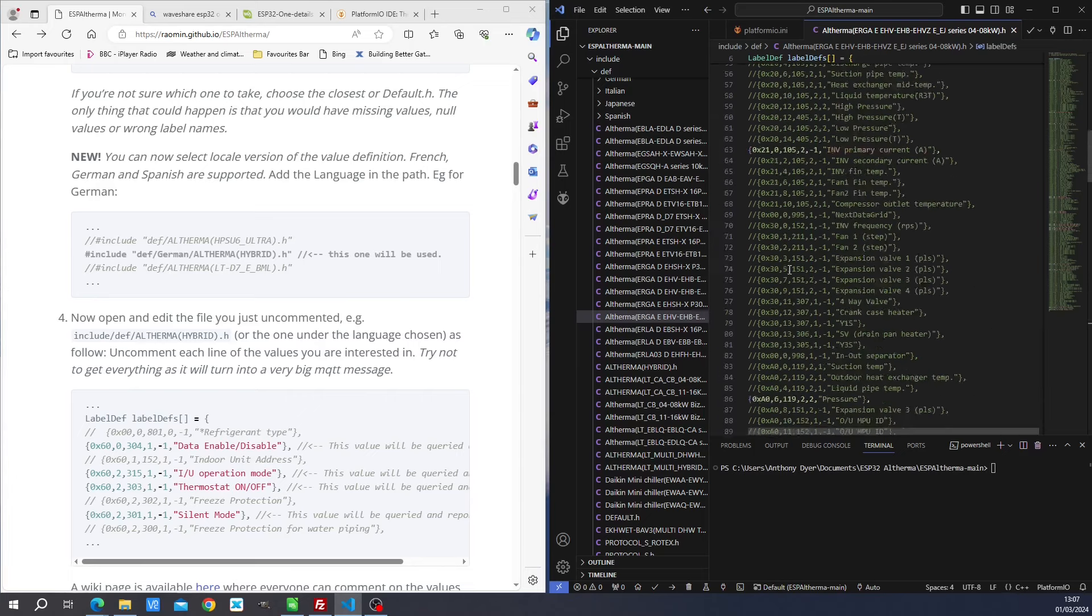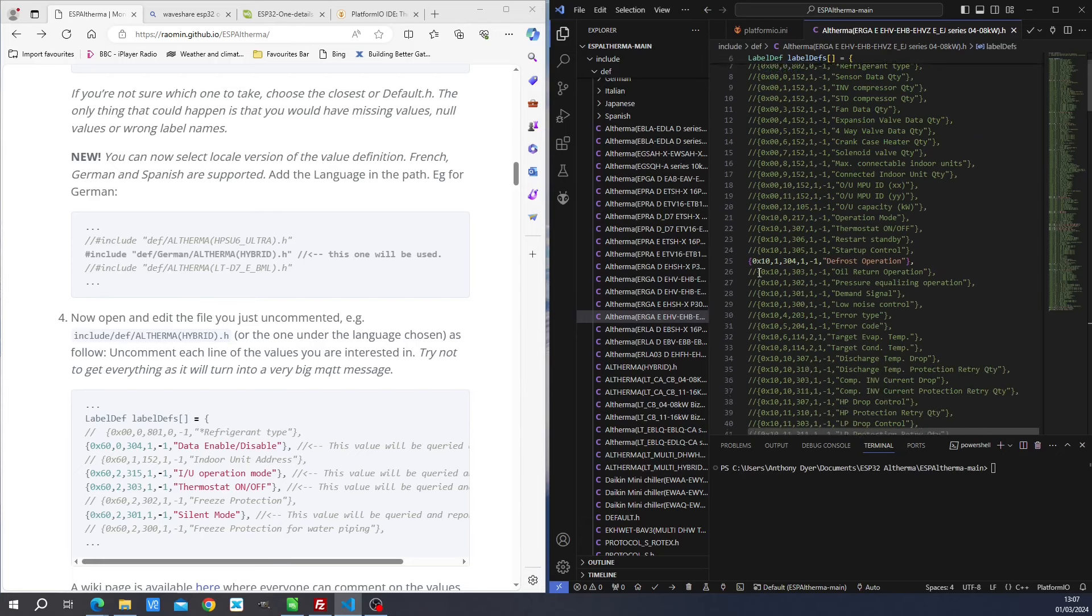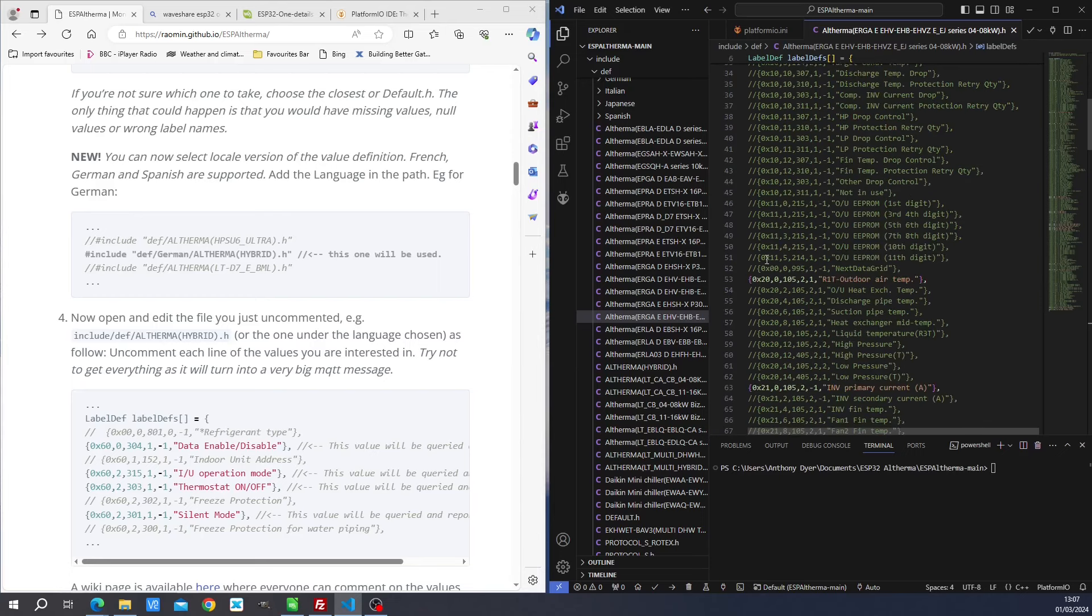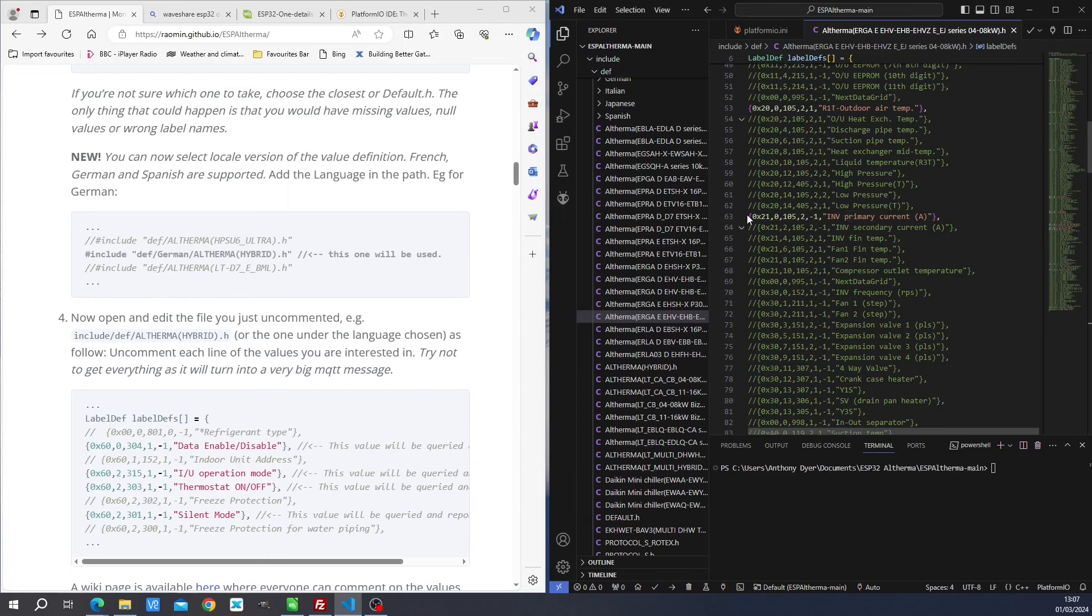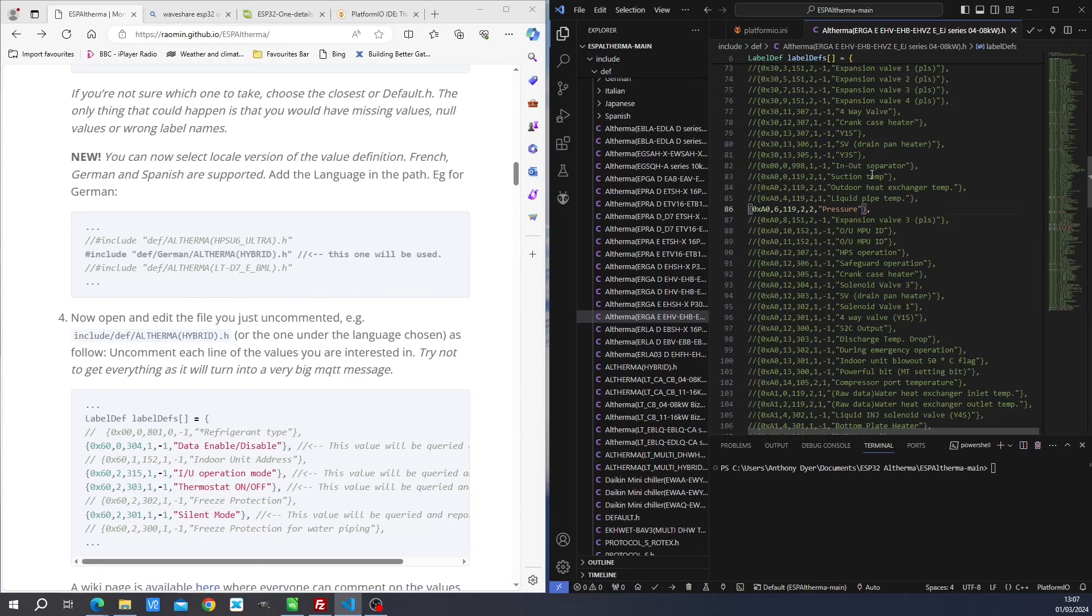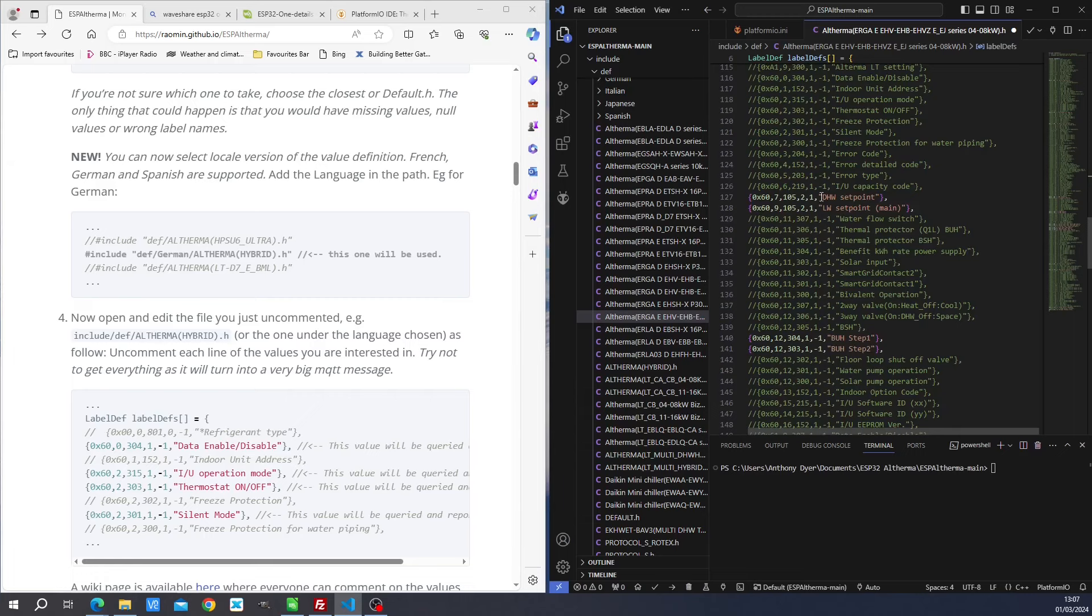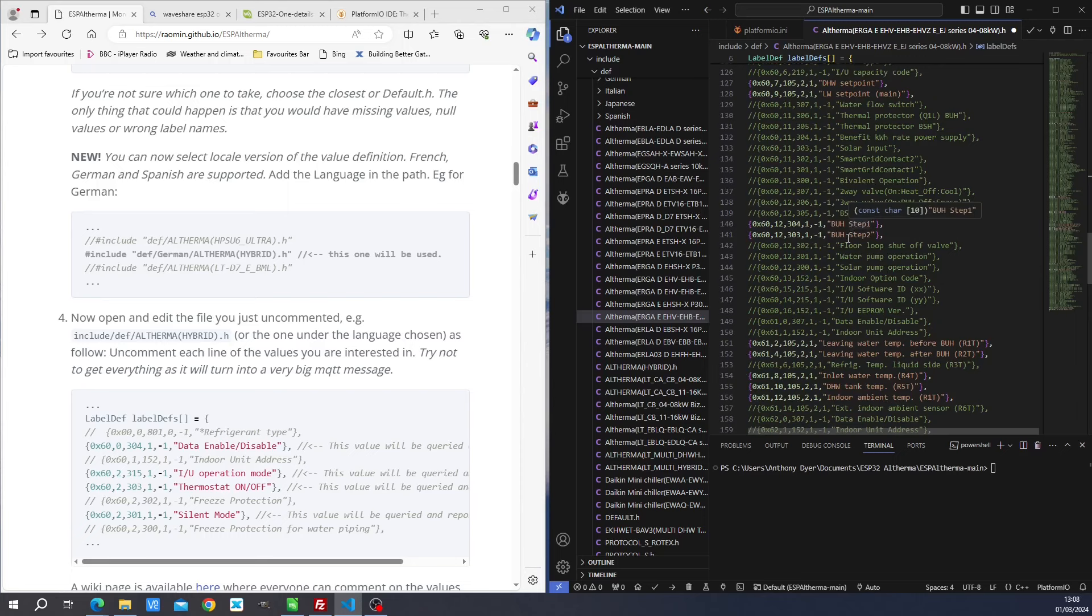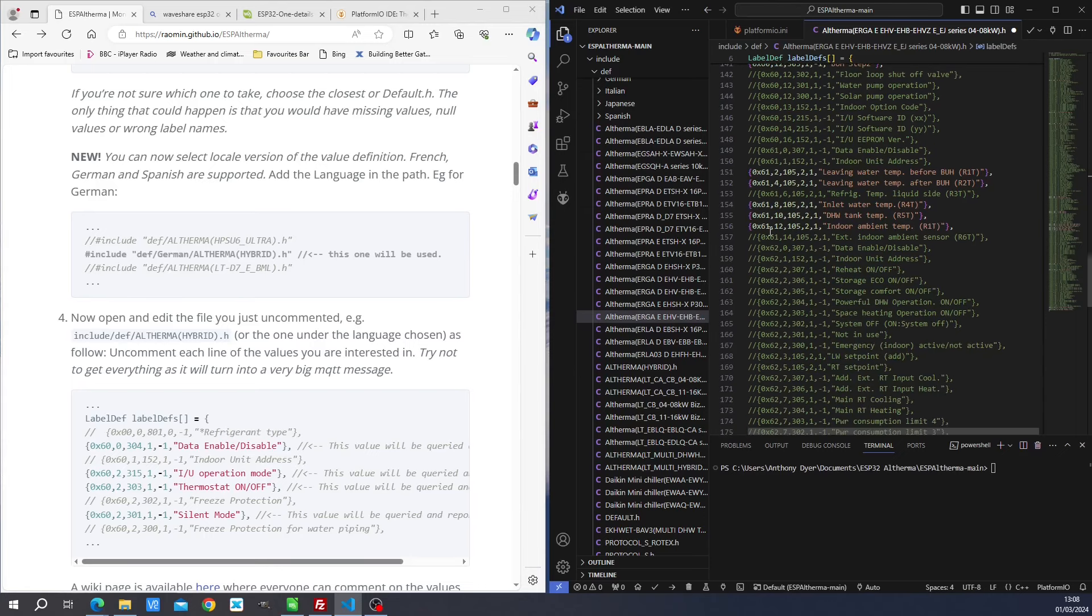What we then did was that we go onto another file here and then we can choose what data we want to extract from here. We've got different operation modes. And in particular, I decided I wanted to look at defrost operation. We've got outdoor air temperature, primary current for the inverter for the main compressor unit. We've got pressure, but I find that that is a value of zero. I'm not too sure what kind of pressure it is. So I'm just going to uncomment it here. Set point for the hot water, leaving water set point, backup heater step one, backup heater step two. So these are the three kilowatt elements for your backup heater. So it's six kilowatts in total. We've got the leaving water before and after the backup heater. You'll remember that from the piping diagram. Inlet water temperature. That is for the return leg of your central heating flow. You've got the hot water tank temperature. Indoor ambient temperature. Flow sensor.